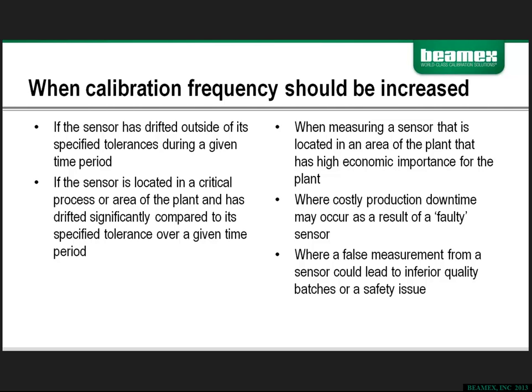And then after that first cycle of 3 months, we would perform some more analysis of that particular asset to determine whether or not there was significant drift over a 3-month period, and to what extent that drift was verified in terms of data. So if it was significant, then we would once again want to reduce that, and more than likely it would go from 3 months to a month. Or at that point, you might want to make the determination that this particular sensor is drifting so much that it might warrant replacement. You might want to evaluate a different manufacturer or model number for that particular sensor, once again based on whether it's in a critical area of the plant or something of that nature.